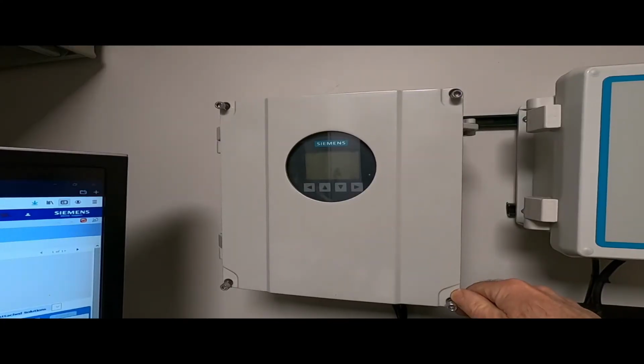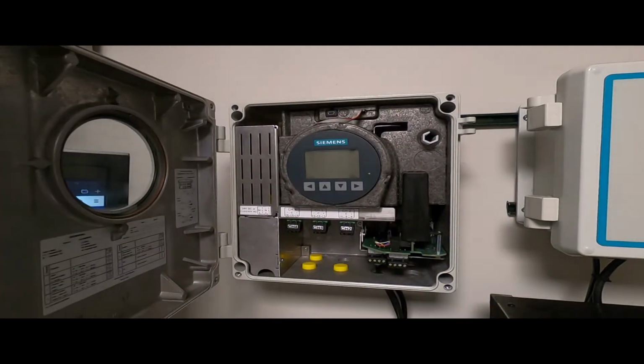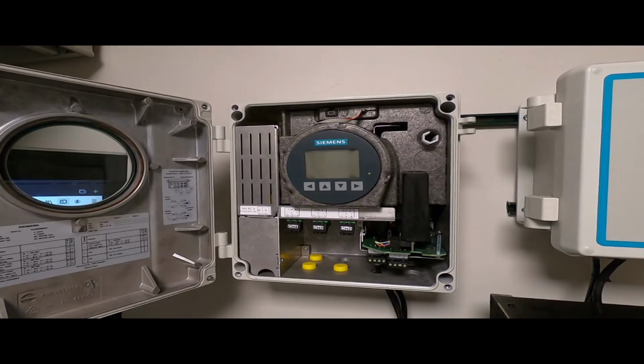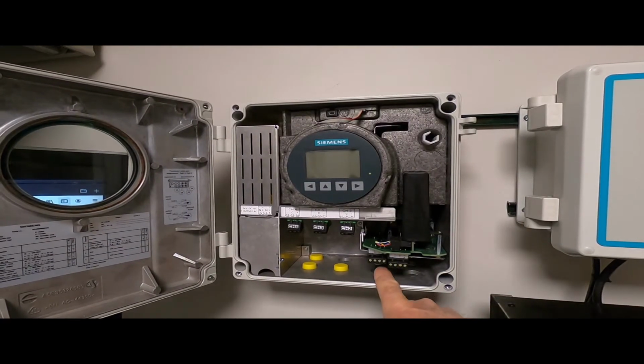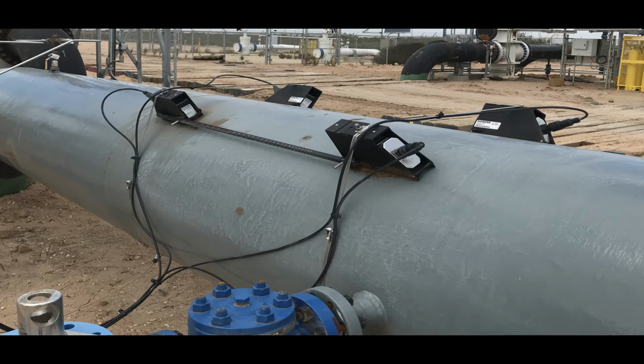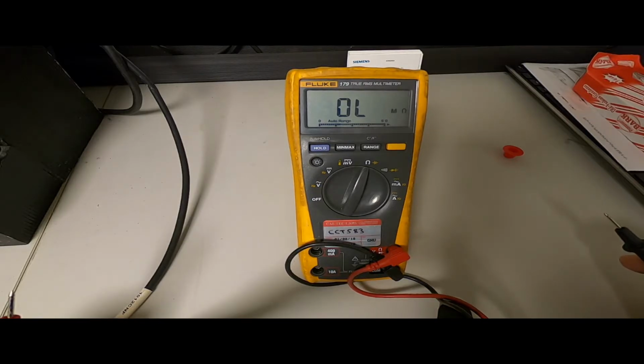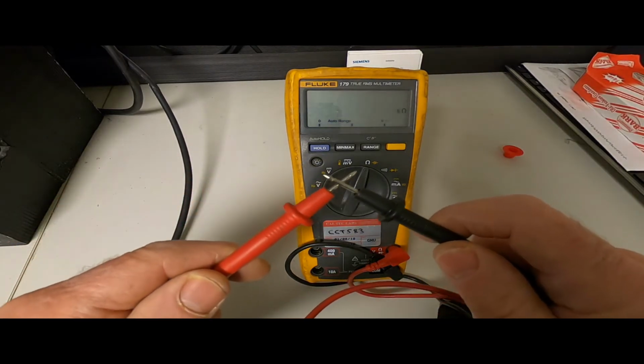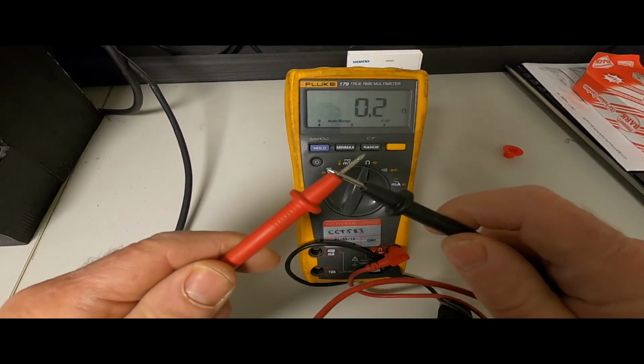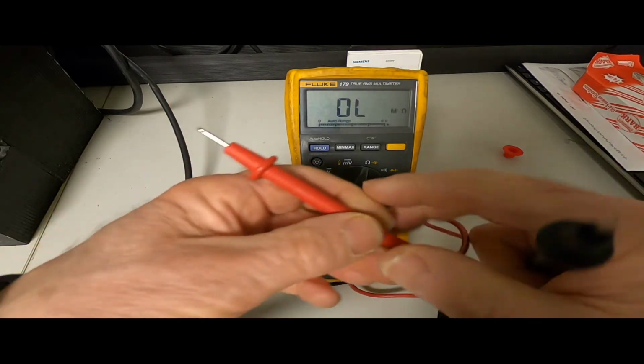To get started with this process, just simply access the flow meter with which you're having problems and remove the flow sensor cables from the flow meter itself. Leave the end connected to the transducers alone. With your flow meter cables disconnected from the meter itself and your ohm meter on and available, of course, do a quick check with your ohm meter just to make sure that it is responding, which it is.